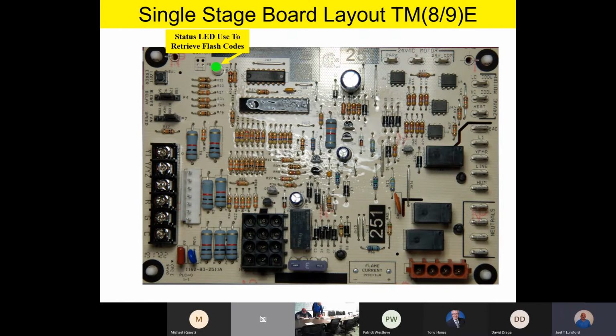And to give an example, if you have like a 3 flash code, that tells you there's something going on with the pressure switch, so you may have a venting issue. If you have like a 4 flash code, that means it overheated, and so on. So by looking at the flash codes and counting the flash codes, it really helps narrow down what's going on with the furnace. If you have some safeties that have tripped, or some airflow issues or what have you, and the heat exchanger is overheating, and so on. But those flash codes are very, very handy.